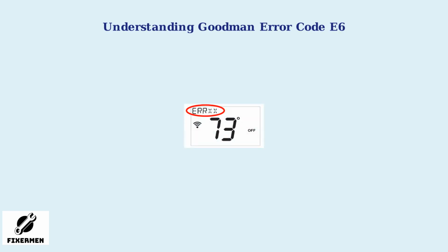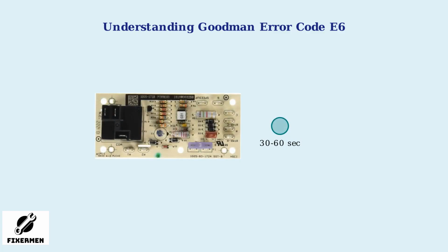Goodman Error Code E6 signals an indoor fan motor lockout. This means the blower motor responsible for circulating air has failed to start or is locked, preventing proper airflow. This error is common in Goodman air conditioners, heat pumps, and furnaces. The unit's control board detects this failure because the fan motor doesn't spin within 30 to 60 seconds of startup. The lockout triggers to prevent compressor damage from overheating due to lack of airflow.